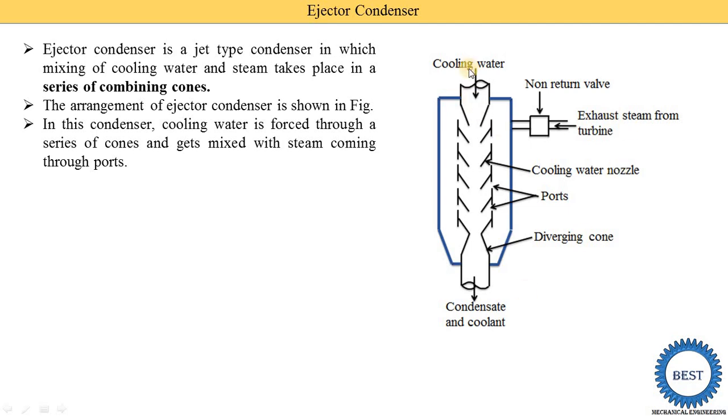This cooling water supply is passed through the various cones or nozzles. We know that in the nozzle, the kinetic energy is increased and the pressure energy is reduced. When this pressure is reduced here, steam from this side is supplied in these cones or nozzles and the mixing of the steam and cooling water takes place.